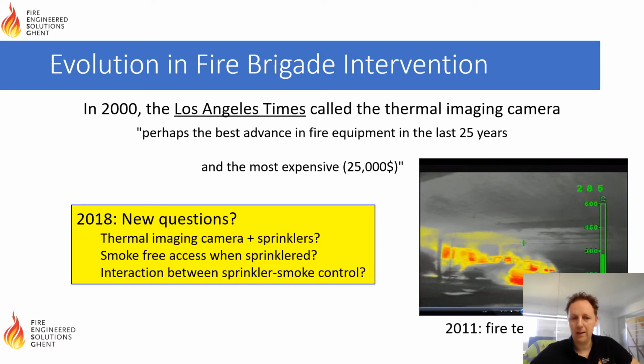If we look at 2018, when we started this research project, there were new questions. Every fire brigade corps at that point had a thermal imaging camera. It was part of their standing operating procedures. There were questions like, would sprinklers have a negative impact on the thermal imaging camera? Is it still required to have a smoke-free access when the car park is sprinklered? And then more general, what is the interaction between sprinkler and smoke and heat control? Do they affect each other in a positive or a negative way?